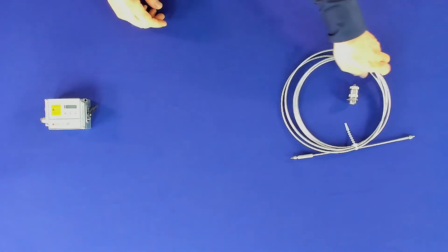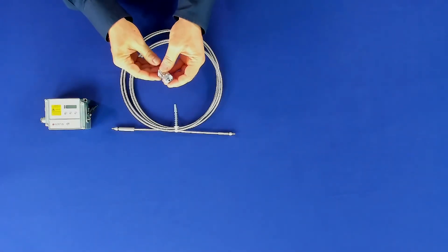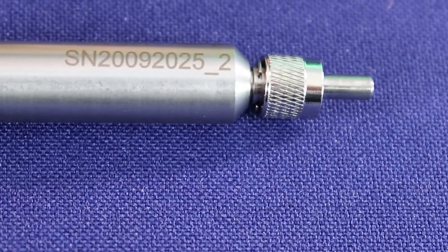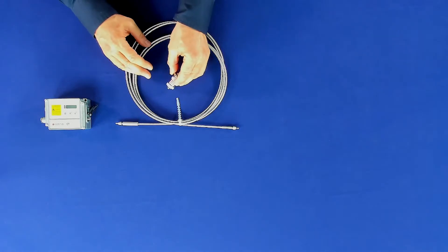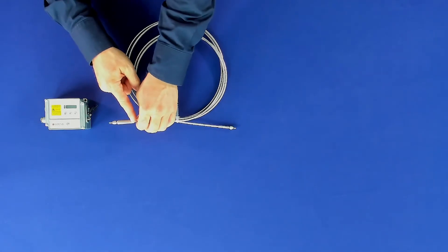With a spare fiber you will also get a spare sensor head. The serial number of the device is located on the sensor head and on the fiber cable on the side of the electronic box. Each head and associated fiber has its own unique number for identification — so this could be one, two, or three. Please be sure to use the same serial number on the sensor head and on the fiber cable.